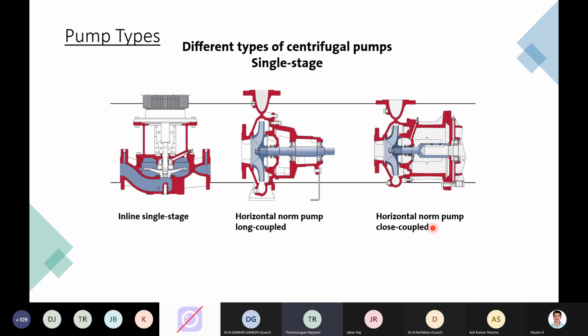So now we touch upon some of the products in the pumping application: what pumps are available, where you can use them, and what the recommendation would be. In terms of pump types, in the centrifugal category we have inline single stage, horizontal end suction pumps, and horizontal close coupled pumps. I think these would be predominantly seen in water transfer applications, even MCW, ACW, auxiliary pumps, or DM water transfer. Many of the pumps will be horizontal end suction.